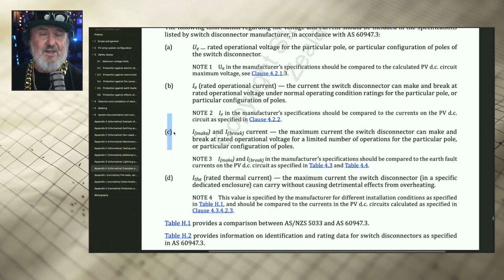So I guess what it's saying is that a DC switch disconnect is really an emergency switch or a maintenance switch. It's not something that you would do every day. You don't turn it on and off every day because you'll soon get over that probably very low bar in terms of its ability to continue to operate. And if anyone's ever done this in a slightly dim room, you can actually see the arc inside the enclosure sometimes. It sort of makes a lovely sound as it interrupts the arc, and there's a little bit of a glow inside the enclosure. It's doing some hard work. So that's I make, I break. And those values are always a lot higher than IE, the operating current.